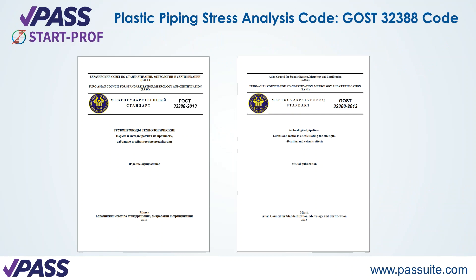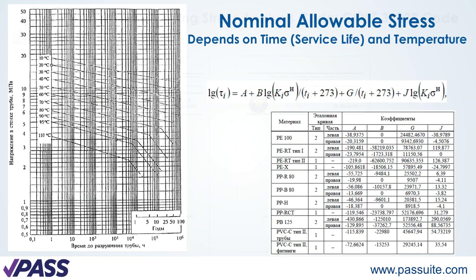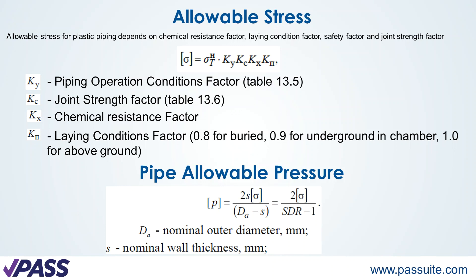The analysis is done according to the Russian GOST code for process piping, which includes a special paragraph about plastic piping stress analysis. The allowable stress for plastic material depends on service life and temperature. Here you can see the special equation that is used to determine the allowable stress.